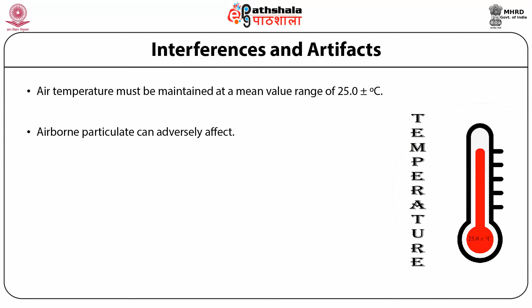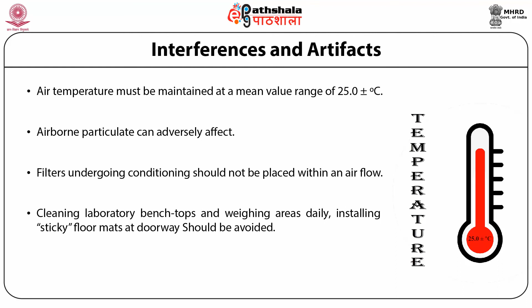The filters undergoing conditioning should not be placed within an airflow path created by air conditioning, ductwork, computer printers, or frequently opened doorways. Clean the laboratory, bench tops, and weighing areas daily, install sticky floor mats at doorway entrances to the balance room, and wear clean lab coats regularly. Clothing can further minimize dust contamination.